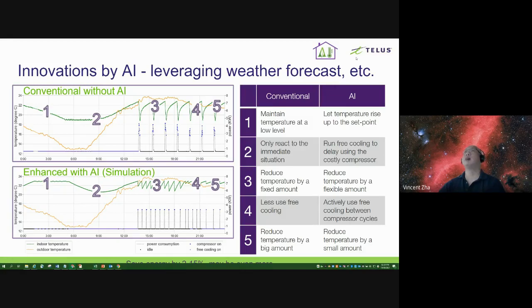Number 3, every time running the compressor, the agent pulled down the temperature by a flexible amount. Number 4, the agent more actively leveraged the free cooling. Number 5, the agent reduced the temperature by a smaller amount when running the compressor.